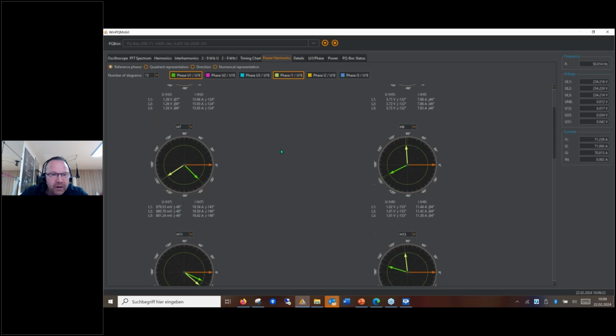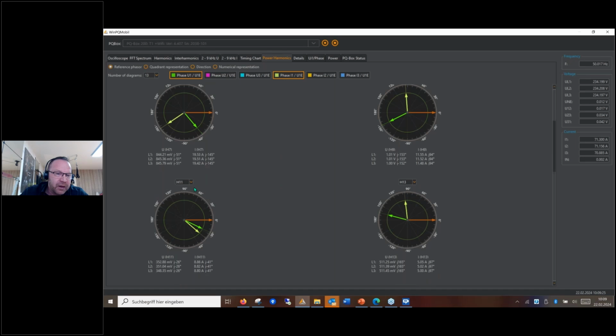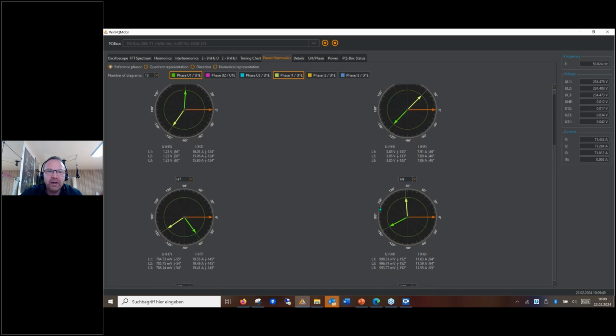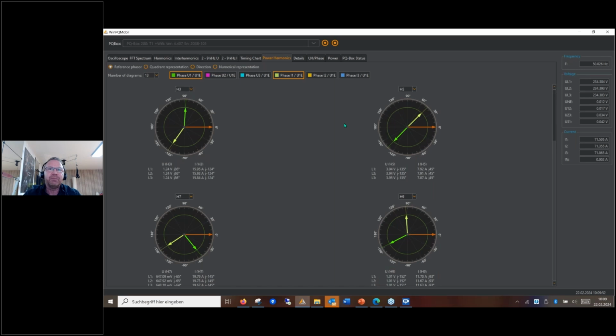So I go down. If I choose the 11th harmonic, for example, here we see the disturbance in the network on the voltage and the disturbance my machine is at the moment producing. And this is nearly the same phase angle. So if I add both angles and the result is bigger than before, then it is worse for the network. And if it is in this direction, or here for the third and for the fifth harmonic, my device is positive for the network. So to work in this direction is much clearer nowadays to see if a producer of harmonics is positive for the network or negative for the network.